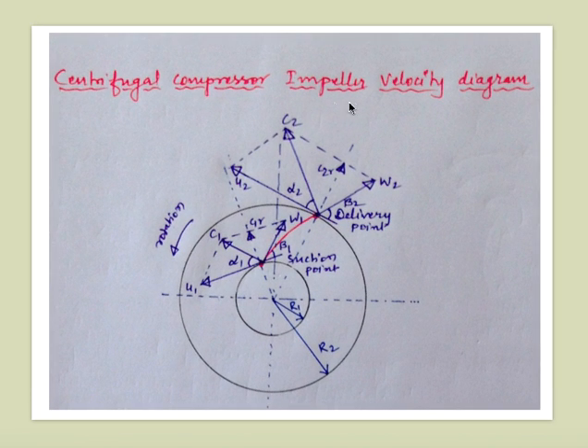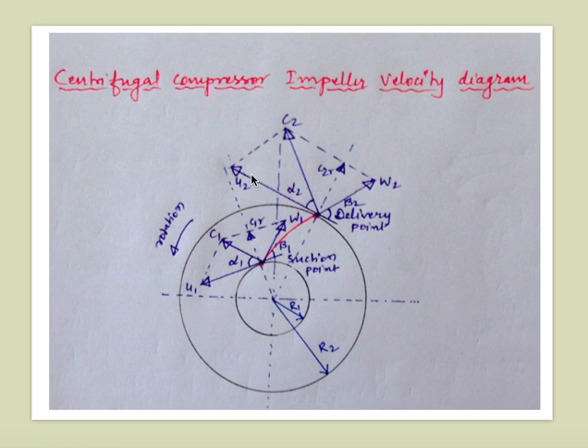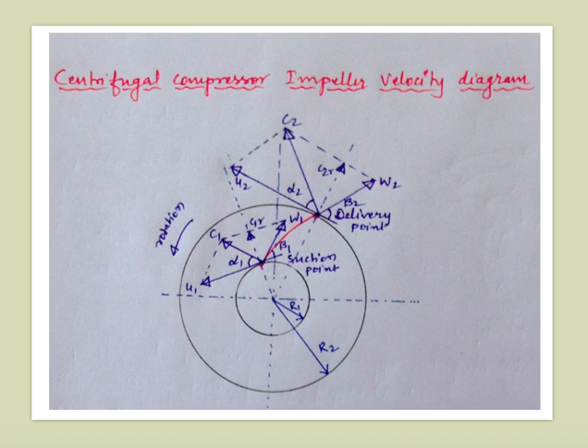The centrifugal impeller velocity diagram is shown in a larger zoomed view. You can see clearly: c1 and c2 as the resultant absolute gas velocities, the radial components c1r and c2r, and the tangential impeller velocities u1 at suction and u2 at delivery. w1 and w2 represent the actual direction of gas flow — w1 is the actual gas velocity direction at suction, and the resultant absolute velocities are c1 and c2 respectively.